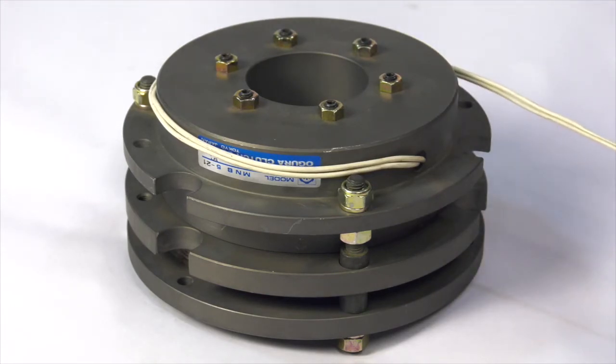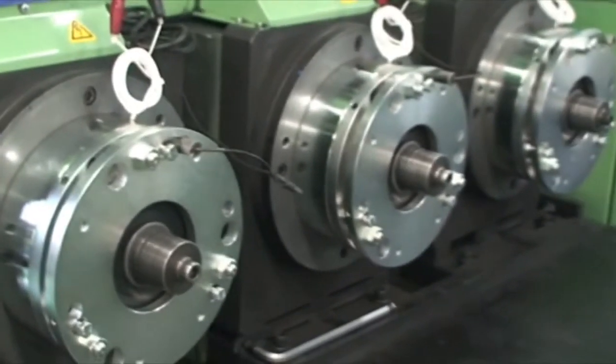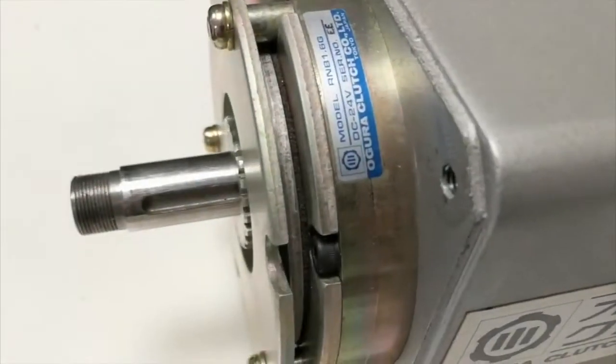Don't wrap the lead wires around the coil housing because high temperature from the housing may damage the lead wires. Cycle the brake under normal load conditions. There should be no noise coming from the brake when it is engaged because there should be no movement.